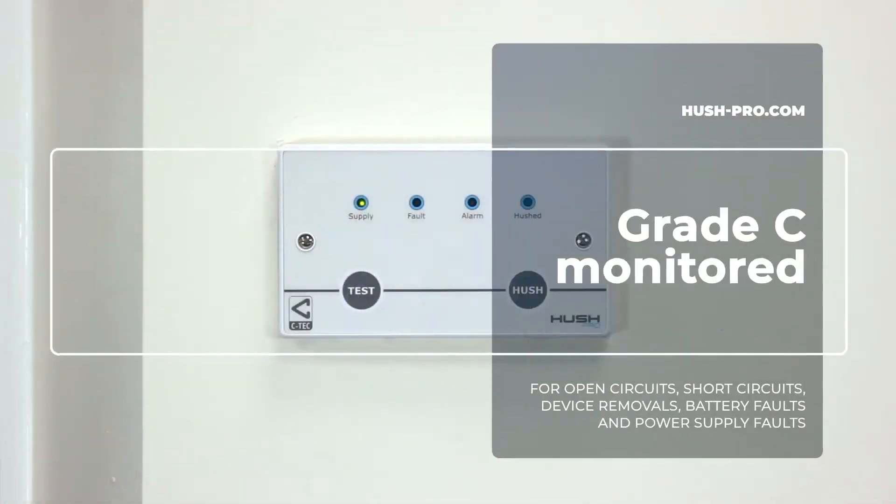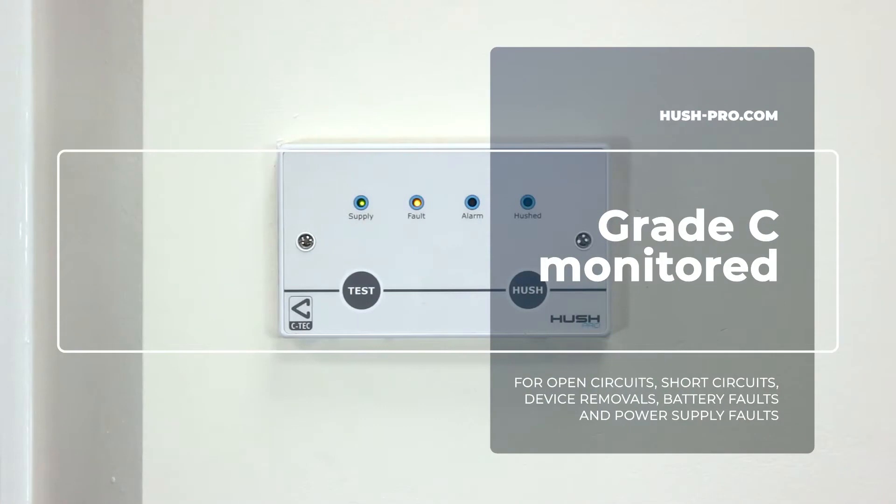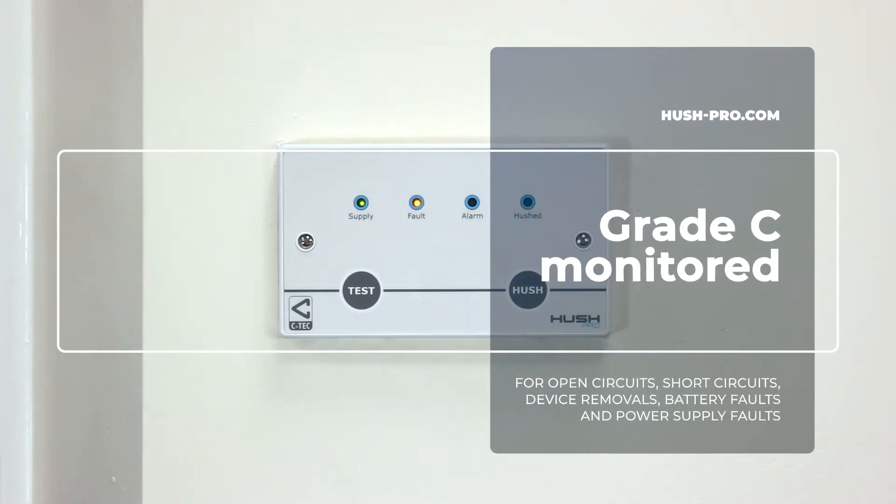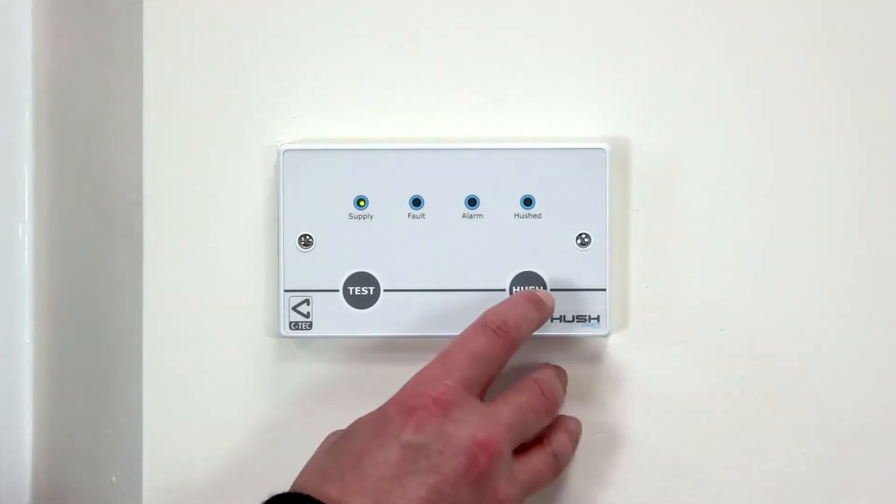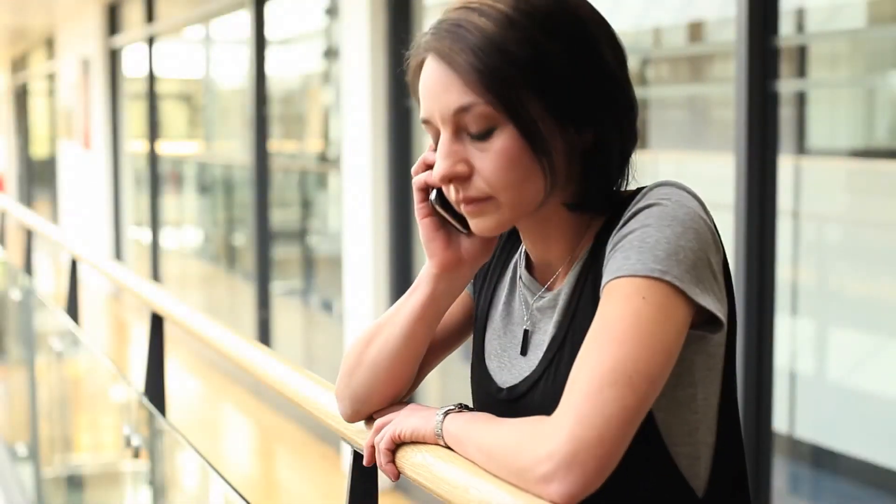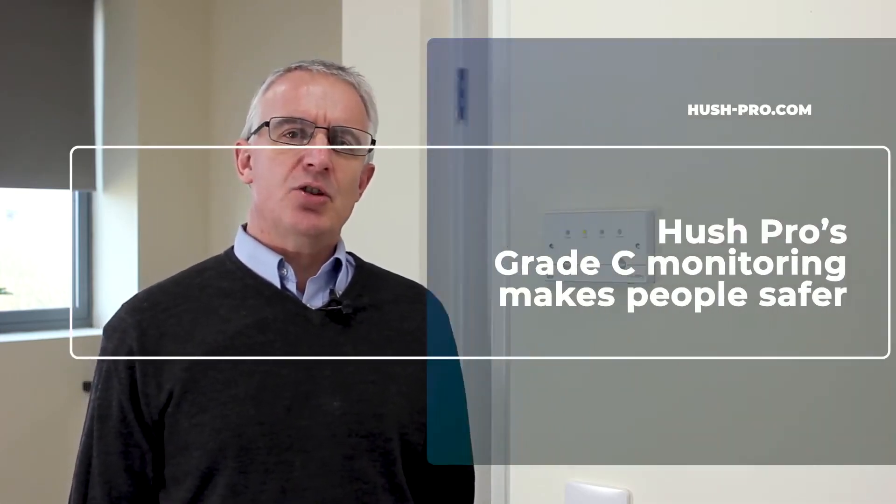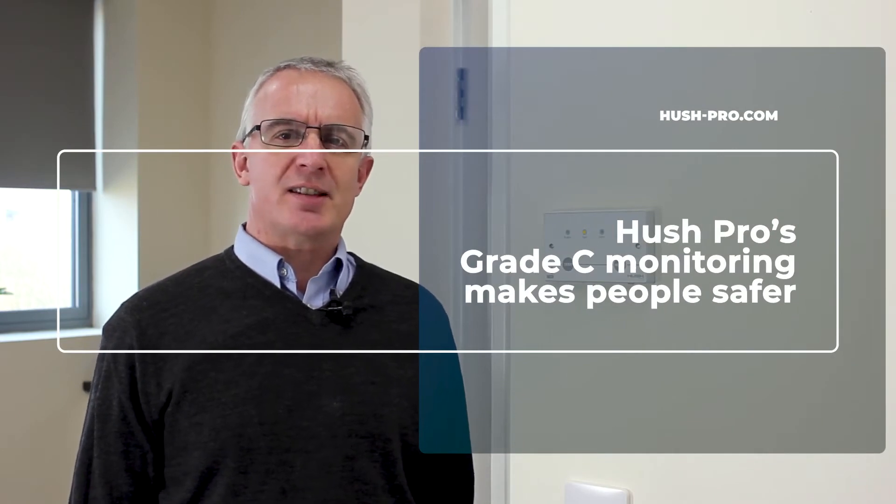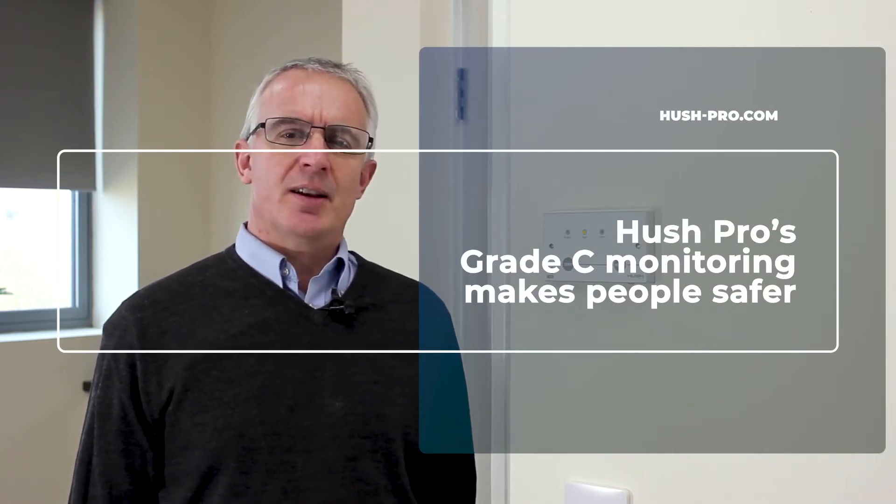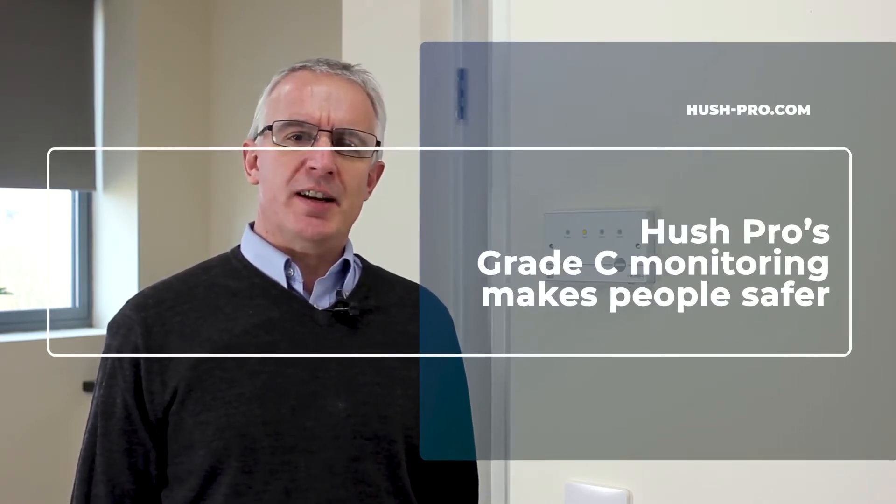Such a fault is brought to the attention of the occupant by a buzzer sounding. The occupant can then come along and press Hush to silence the fault for 24 hours. The idea being they contact their landlord and ask them to fix the fault. If the fault is not fixed, in another 24 hours the buzzer will sound again to ensure the fault is not forgotten about. This ensures the building occupant is aware that their system may be compromised. This level of fault monitoring is not needed or provided on many lower grade systems.